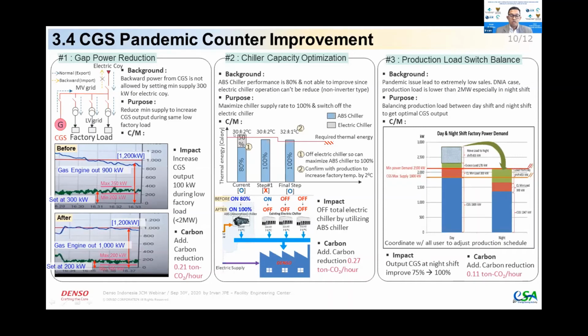Our setting is 30 plus minus 2 degrees Celsius. Step one is we want to turn off the electric chiller. However, that's still not enough. Then we coordinated with our production team, and they agreed to slightly increase the setting temperature by 2 degrees Celsius, so that the ABS chiller is enough to supply the ventilation system. This also achieves additional carbon reduction.